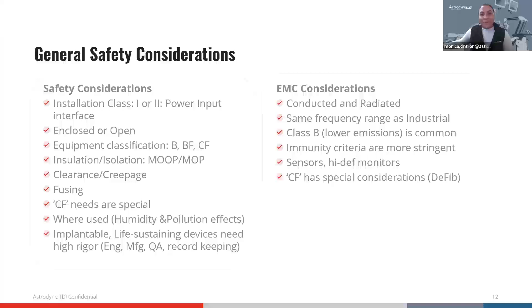This is one of the most important classifications. At the top of the list of all medical system specifications is, where is the part used? Does the human body float, or rather sit on a bed, with absolutely no electrical contact with anything? That's a reasonably safe environment where you're just being monitored, like in an MRI or CT. There are no probes connected to you, you simply lie on a bed and you're not electrically tied. That's the most benign operating mode.